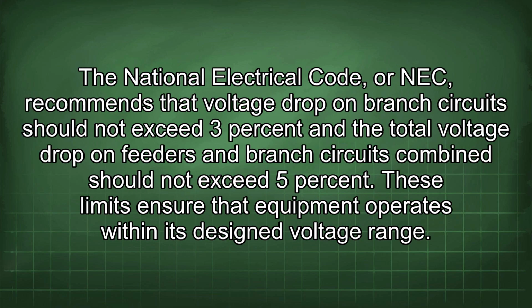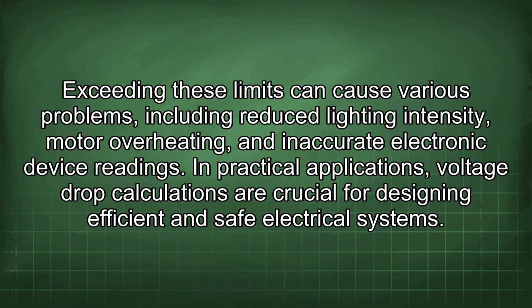The National Electrical Code, or NEC, recommends that voltage drop on branch circuits should not exceed 3% and the total voltage drop on feeders and branch circuits combined should not exceed 5%. These limits ensure that equipment operates within its designed voltage range. Exceeding these limits can cause various problems, including reduced lighting intensity, motor overheating, and inaccurate electronic device readings. In practical applications, voltage drop calculations are crucial for designing efficient and safe electrical systems.